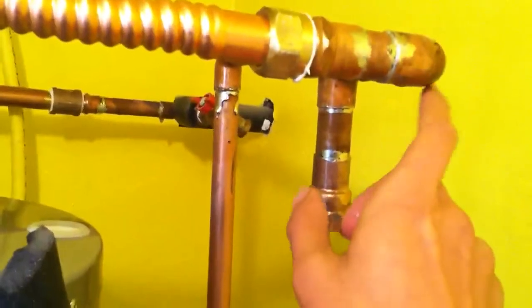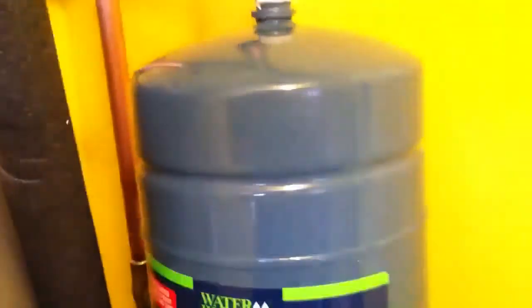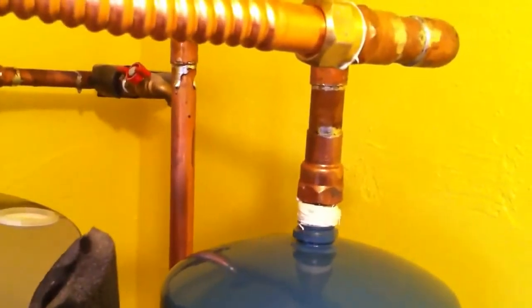I turned off my water and drained it, and I removed the stub on the cold water. Now what I'm going to do — take the safety tank, put Teflon tape and pipe dope on it, and install it on this stub, like so. You always want to make sure that when you install it, you install it on a horizontal run of pipe, not a vertical.